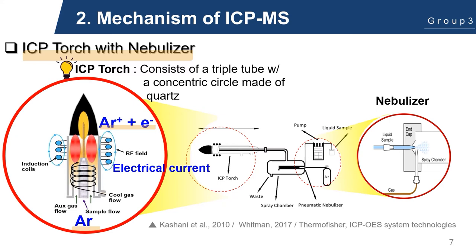So how is plasma formed? The plasma is formed at the end of a set of three concentric quartz tubes, collectively referred to as the torch. Argon gas flows through all three tubes. The inner tube, called the injector, contains the sample aerosol in a stream of argon which delivers the sample to the plasma. Concentric to this is a tangential flow of argon called auxiliary gas, which forms the plasma. The outer tube contains a flow of argon which serves as a cooling layer to prevent the torch from melting.